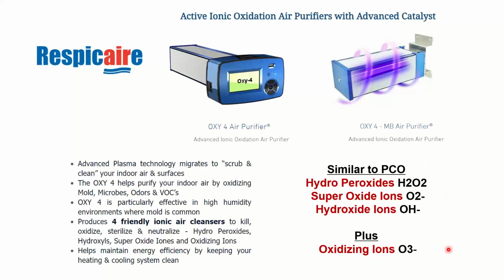Now, you can follow the rules for ozone from FDA, for example. FDA is the most restrictive, I believe, and I want to say it's like 5 parts per billion. I forget what it is off the top of my head. But if you size this correctly for your space, you can keep it underneath that limit and be fine with both OSHA and FDA requirements. Or you can do stupid stuff and put a giant commercial one in a small space and possibly produce too many that can't be utilized. But some people are nervous about it. They don't want any of them. That's fine. You don't give them that.